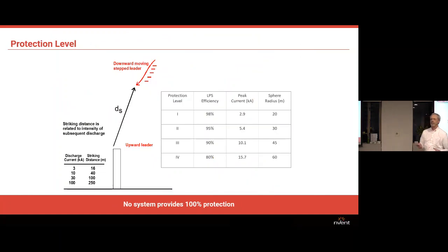Protection levels: we have a choice of 4 protection levels according to the standard, and protection level 1 is the highest and protection level 4 is the lowest. And the second column over on that table, if we go for protection level 3, which in the standard is set as a pretty typical protection level, considered to be standard, it's saying that 90% of lightning in the area should go to the lightning protection system and 10% may not. But that 10% is the weakest lightning. If you go to protection level 1, only 2% may miss the lightning protection system, and that's going to be pretty weak lightning and may not really cause much damage anyway.